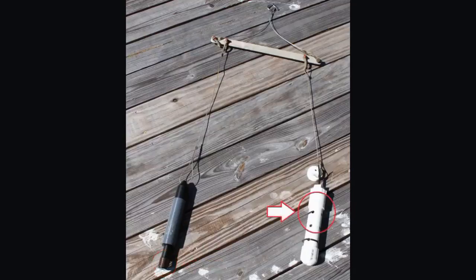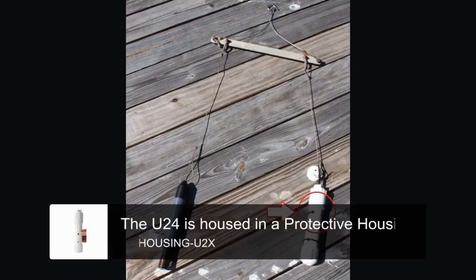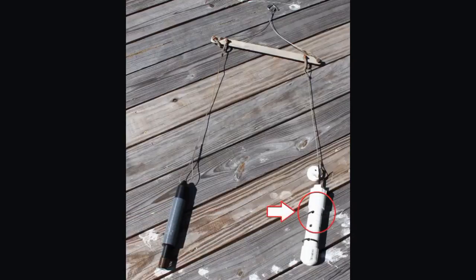And to show you where that conductivity sensor is in the conductivity logger, it is approximately in that location, aligned with that top hole. We put an extra zip tie through there to hold that logger down in that housing so that that sensor will be lined up with that hole. So that's why that extra zip tie is there.